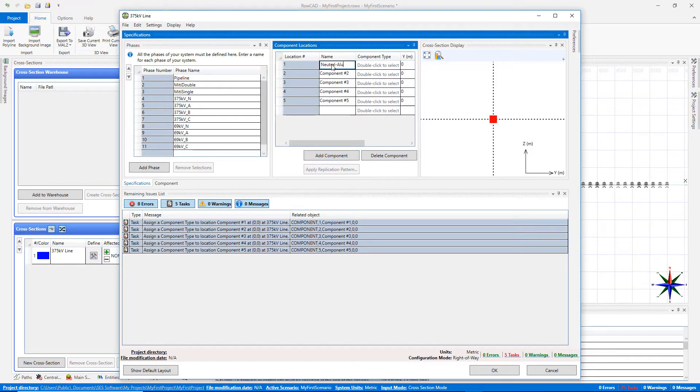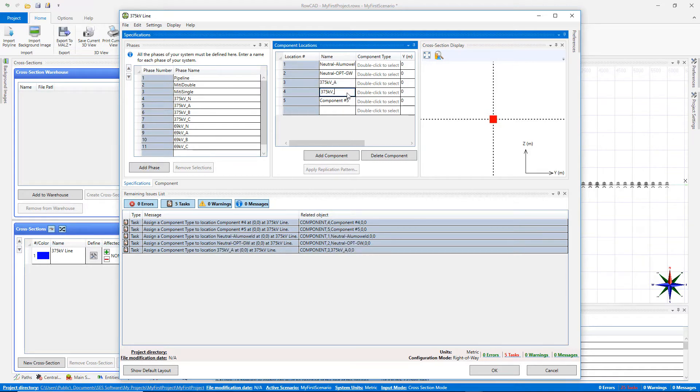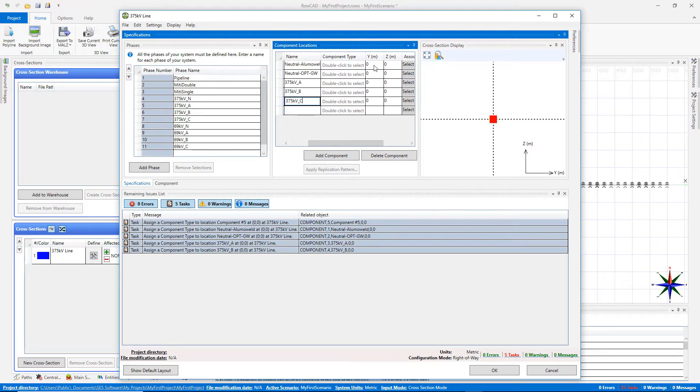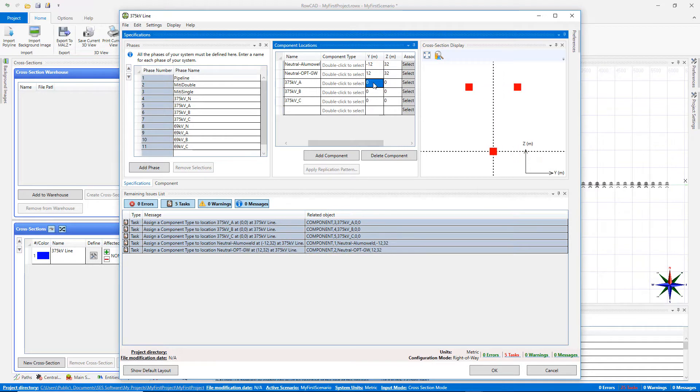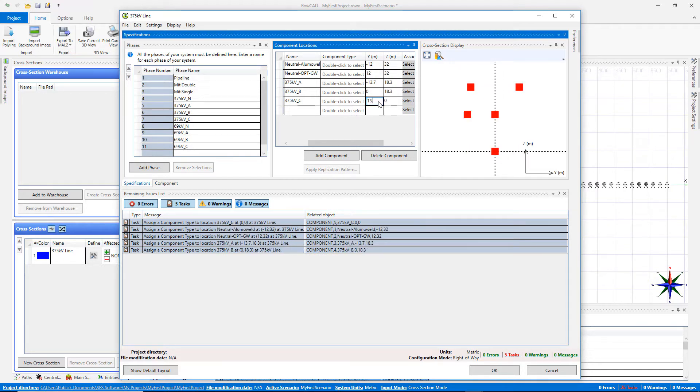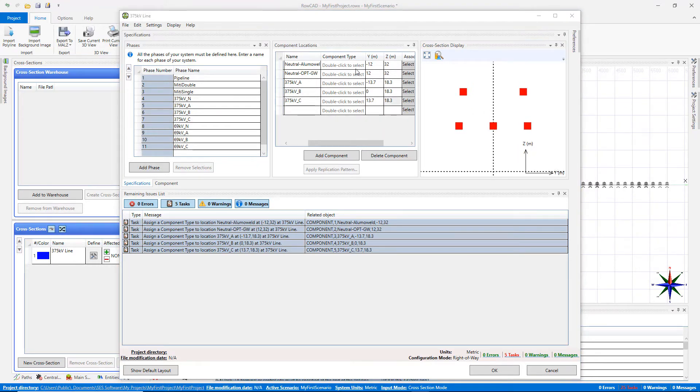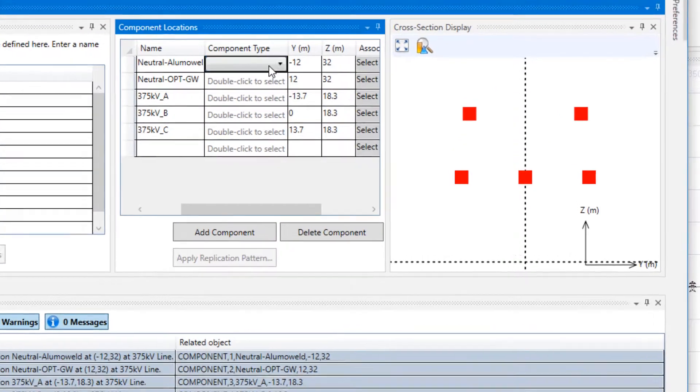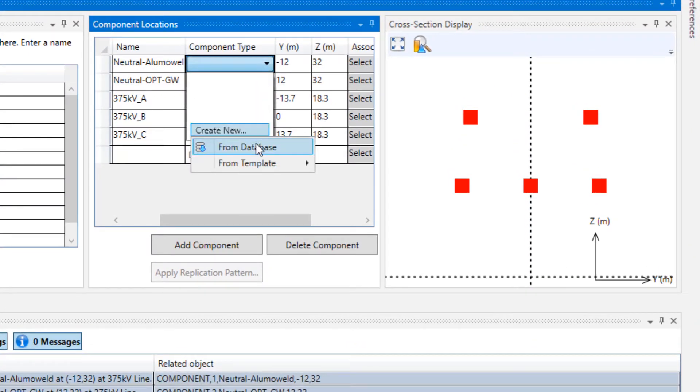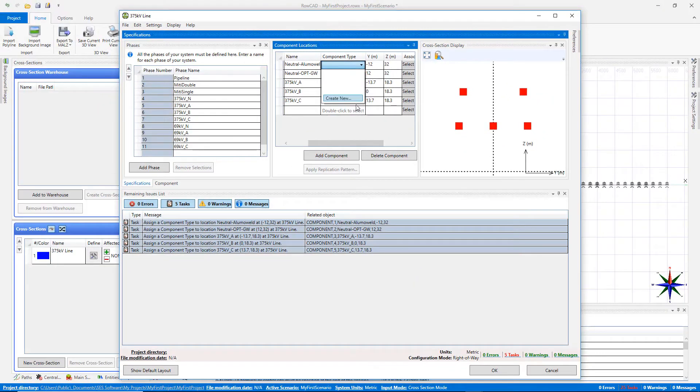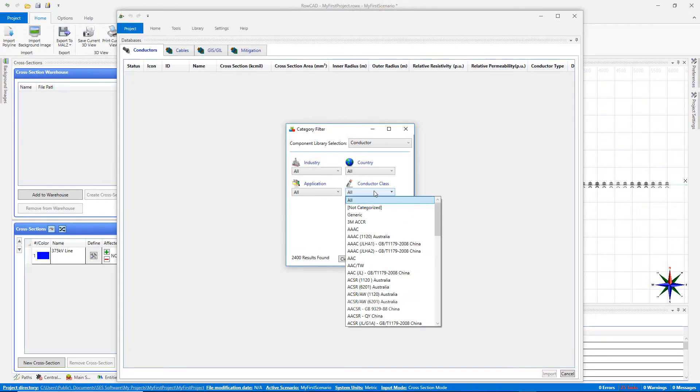The cross-section window opens to perform the cross-section definition. Add a location for each of the components forming the cross-section of this transmission line. Add 2 for shield wires and 3 for phases. Then enter their coordinates. Note that the positive Y coordinates means the right, and negative Y coordinates means the left direction as seen by a person standing on a polyline and looking in the direction of increasing node numbers. Now assign characteristics to the components made of simple conductors.